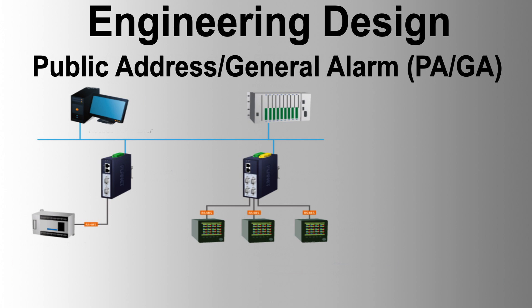GA controller: an intelligent dual microprocessor-based, software-configurable, 19-inch rack-mount type controller. Provides continuous monitoring for up to 16 master/local paging panels and interacts with intelligent power amplifiers. Includes hot standby amplifier control, PBX access, page party access, beacon control outputs, and a web server board for remote monitoring.